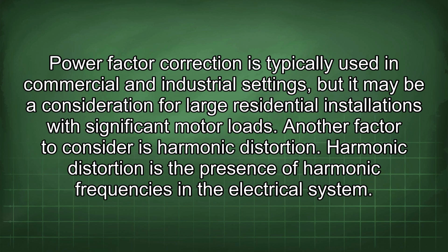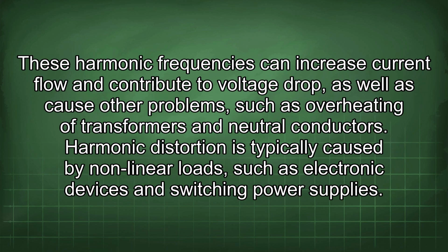Power factor correction is typically used in commercial and industrial settings, but it may be a consideration for large residential installations with significant motor loads. Another factor to consider is harmonic distortion. Harmonic distortion is the presence of harmonic frequencies in the electrical system. These harmonic frequencies can increase current flow and contribute to voltage drop, as well as cause other problems, such as overheating of transformers and neutral conductors.